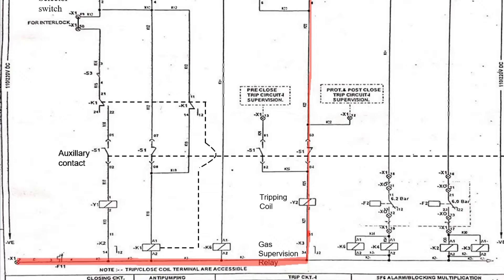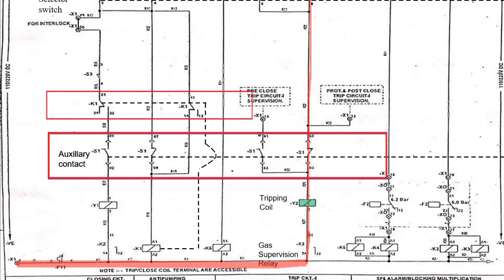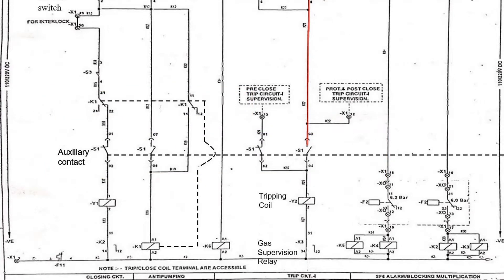Thus energizing the tripping coil, and as soon as the circuit breaker trips, its auxiliary contact along with K1 relay — which is the anti-pumping relay — will change its contact as shown here. So with this, it completes our tripping circuit in remote mode.